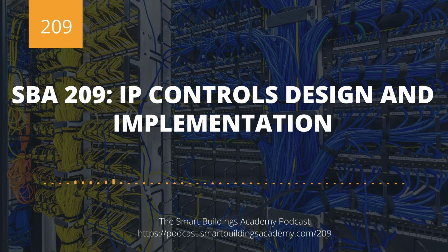Now, once I've got all that done, I've gone through my design, I've laid it out, I got my submittals approved, I've actually implemented, then we want to perform proper checkout. And checkout includes scanning your IP addresses, making sure that your IP addresses are associated with the correct field controllers, and that the appropriate field controllers are associated with the appropriate MAC addresses, and then making sure the appropriate MAC addresses are associated with the proper ports. So it's not like with MSTP controllers where you simply need to know the MAC address for the field controller and then its device instance if you're doing BACnet, and you're good to go.